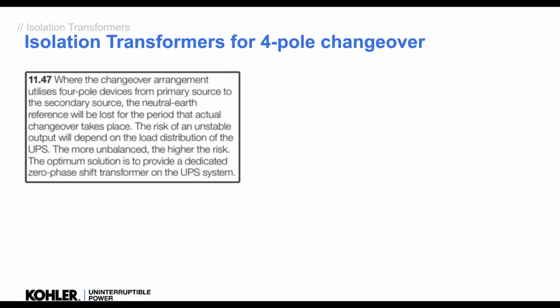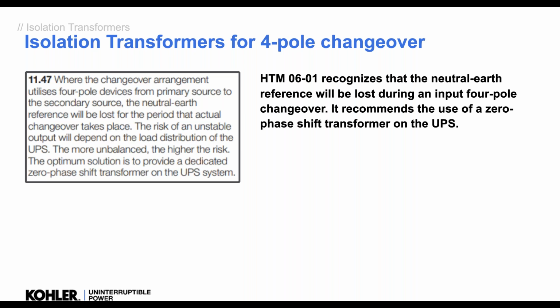Okay, now the second need for an isolation transformer, which is quite a primary one, is where we use 4-pole changeover devices in the upstream distribution to the UPS. Okay, HTM says that neutral earth reference will be lost for the period of the changeover. This risk of unstable output will depend on the load. The more unbalanced, the higher the risk. And the optimum solution is to provide a dedicated 0 phase shift transformer on the UPS.